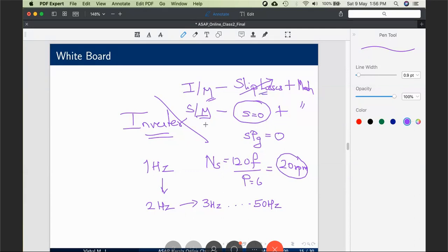Why? Because we are feeding, say, 220 volt DC, and the maximum field current would be 1 or 2 amperes only. So the maximum loss you can experience is hardly less than 500 watts, whereas slip losses will come into kilowatts of power for high power machines. That's why a synchronous machine is far more efficient than an induction machine. Now we can get away with the excitation loss as well.